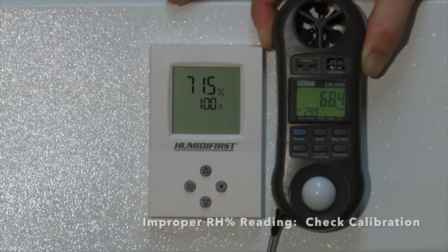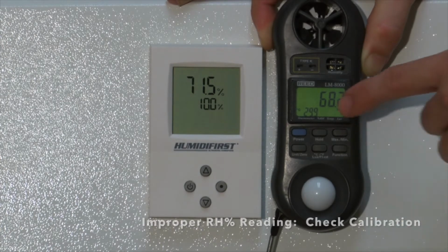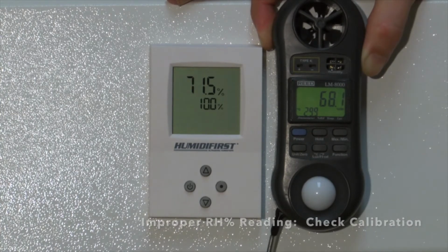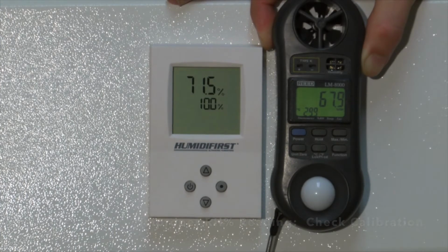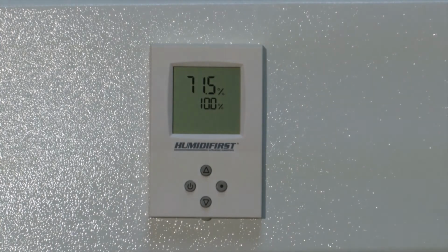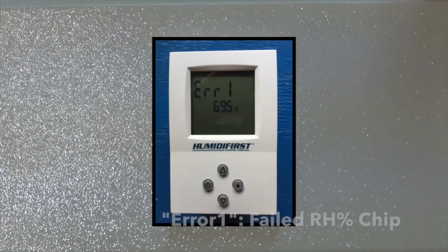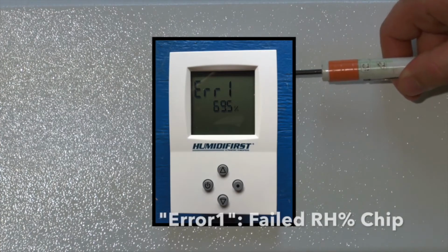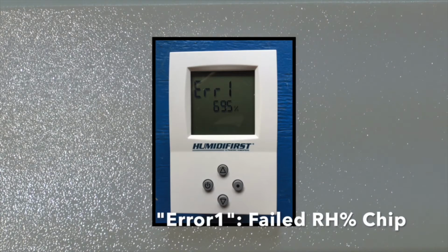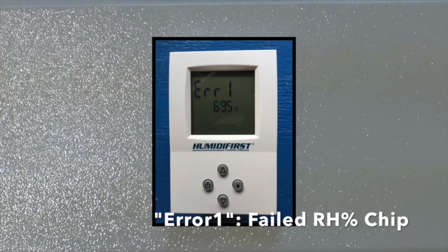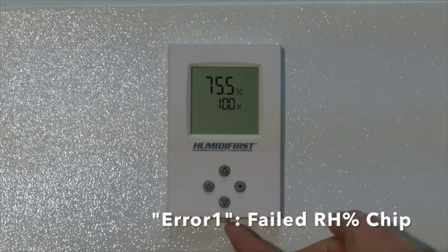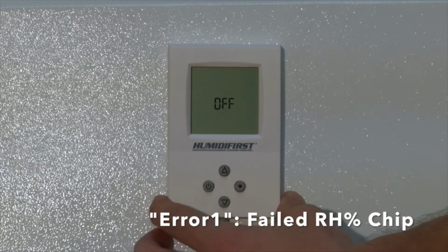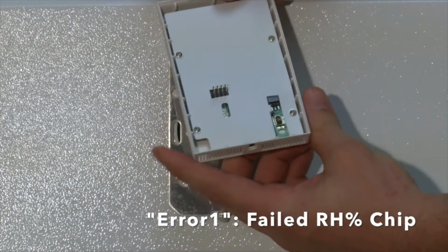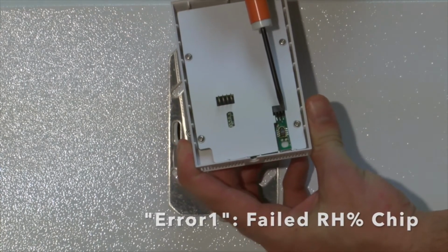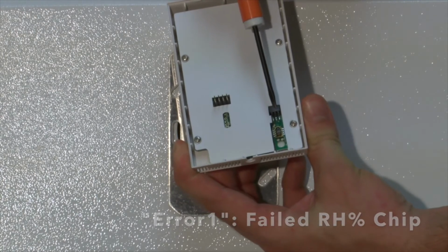Turning the humidistat back on, you will see our reading of 68.3 and 71.5, much closer. Note that 2 relative humidity sensors will almost always read slightly off. This is just the nature of relative humidity sensors. If you ever see an Error 1 message in your humidity reading, this means the actual humidity sensing chip in the humidistat has failed, is damaged, corroded, and is no longer useful. You can remove the small set screw at the bottom of the humidistat to remove the faceplate. You will see the humidity sensor chip in the bottom of the humidistat. This is meant to be replaceable for this scenario.